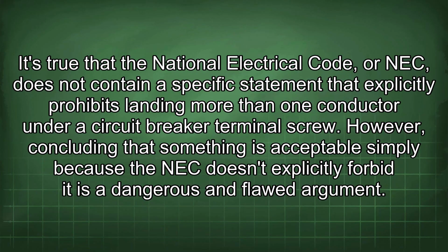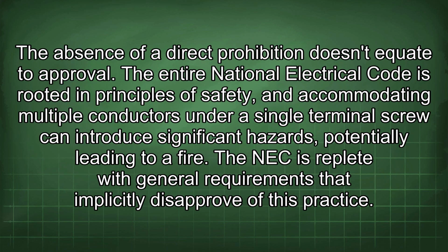It's true that the National Electrical Code, or NEC, does not contain a specific statement that explicitly prohibits landing more than one conductor under a circuit breaker terminal screw. However, concluding that something is acceptable simply because the NEC doesn't explicitly forbid it is a dangerous and flawed argument. The absence of a direct prohibition doesn't equate to approval.